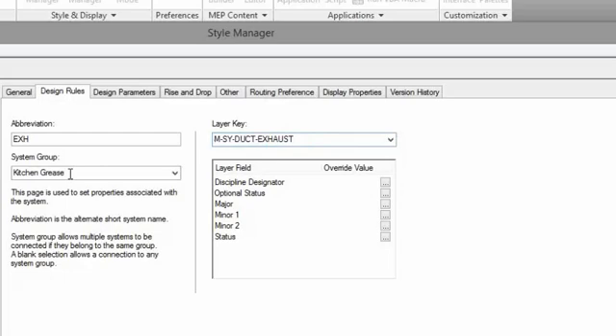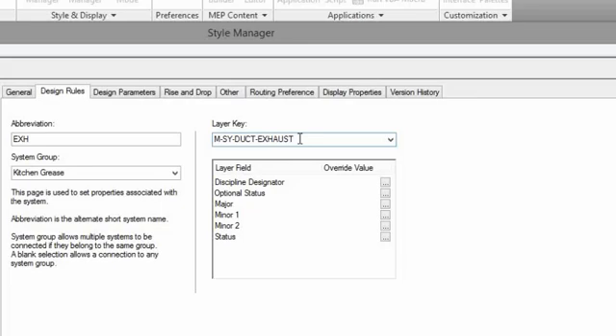The layer key is what sets your layer. And we've spoken about layer keys in the past. And again, we can find them more in depth on our portal website. But basically, the way a layer key works is when you start the duct add command and you choose your system, it looks at the layer key and finds the layer that is assigned to that layer key. It then looks in your drawing and says, does that layer already exist? If it already exists, then it does nothing else. If it doesn't exist, then it creates that layer based on the settings inside of your layer key style. So what's important to note about that is if you already have a drawing that has a layer in it and you go into your layer key style and you make changes to that layer, it is not going to update in that drawing. You would need to purge that layer out of your drawing and then start the duct add command again. And then it will find that that layer is not in the drawing. Then it will create that layer based on the settings.